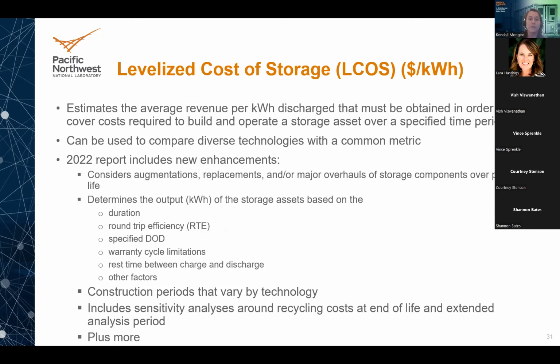In addition, we've fine-tuned how we determine the output of the storage asset, now including items such as duration, round trip efficiency at the specified depth of discharge it's operating, and warranty cycle limitations. For example, if your battery system warranty limits how many cycles per year you can operate to still maintain that warranty, we've involved that. We also include rest time between charge and discharge, which varies by technology, as well as power capacity and energy duration combinations in some instances.